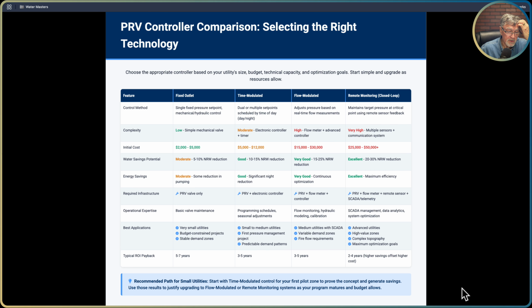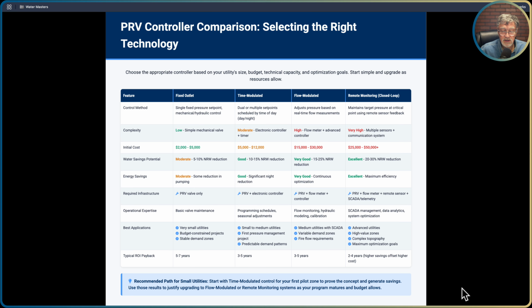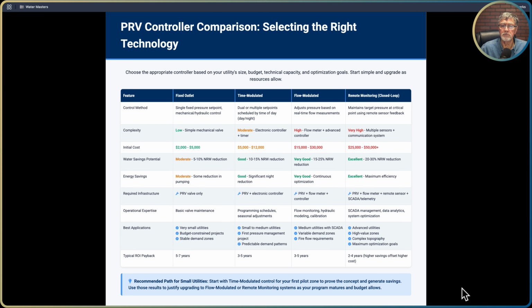Recommended path for small utilities: start with time modulated control for your first pilot zone. So you're going to want to work on that and get that concept down, generate savings. And then if you want to move on to some of your other zones and do some of these more complicated techniques, you can do that. Using just time modulated may be sufficient to do what you need it to do if you have pretty predictable demand and not lots of fluctuations. But if you're seeing a lot of fluctuations, you may want to look at some of these more advanced methods.